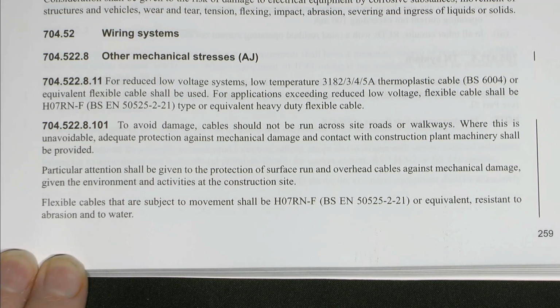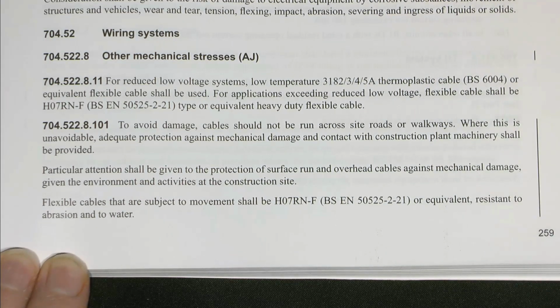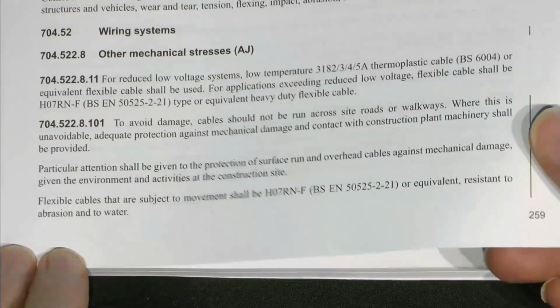Cables should not be run across site roads or walkways. Where this is unavoidable, adequate protection against mechanical damage and contact with construction plant machinery shall be provided. Particular attention should be given to the protection of surface run and overhead cables against mechanical damage. That particular sentence is basically what was there previously. And flexible cables subject to movement shall be one of those or equivalent, resistant to abrasion and to water.